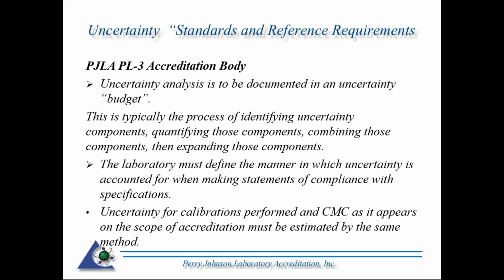Okay, PL3, that's PJLA's policy for measurement uncertainty. Uncertainty analysis is to be documented in an uncertainty budget. And what is this? This is typically the process of identifying uncertainty components, quantifying those components, combining those components, then expanding those components. The laboratory must define the manner in which the uncertainty is accounted for when making statements of compliance with specifications. Again, that resorts back to taking measurement uncertainty into account when making those statements.